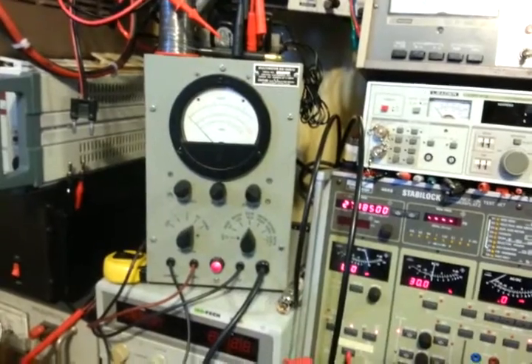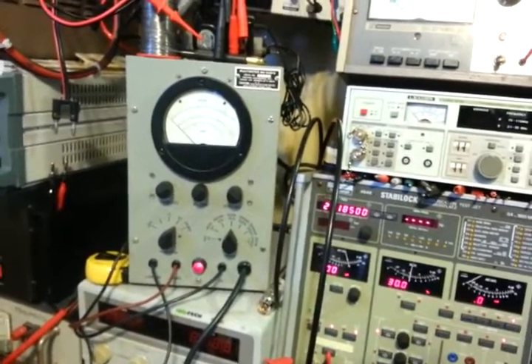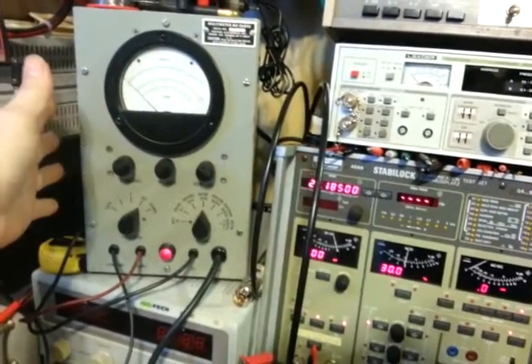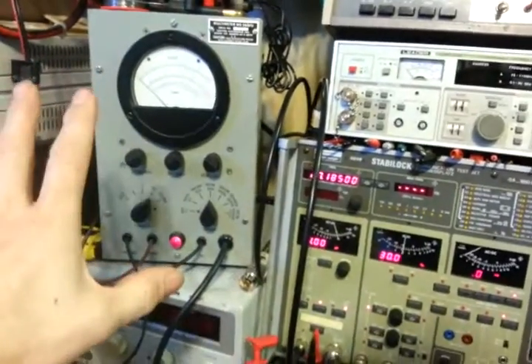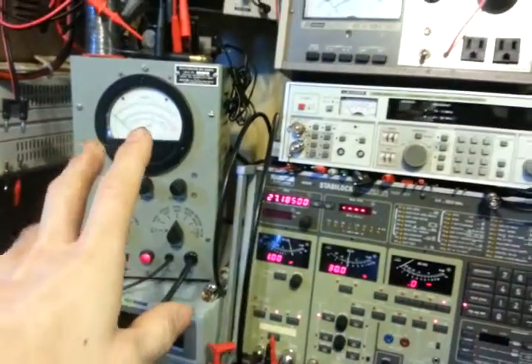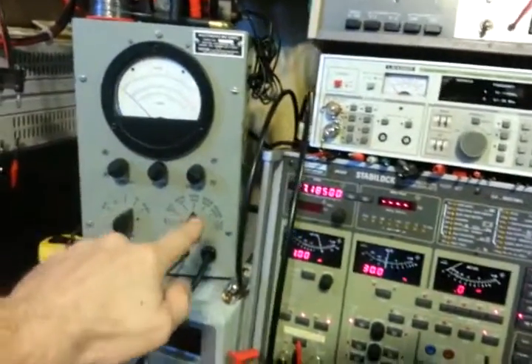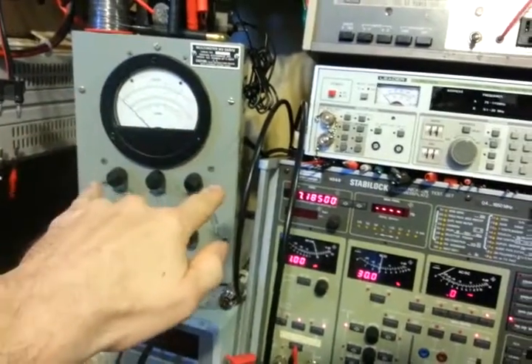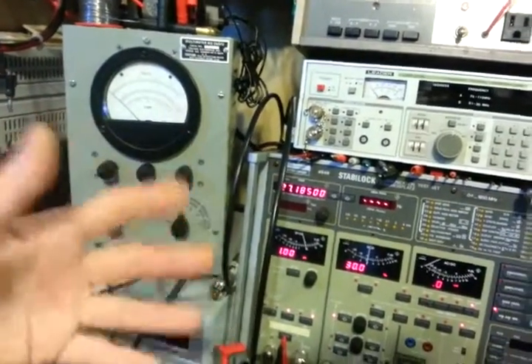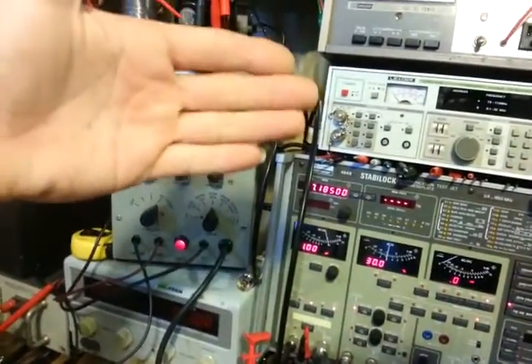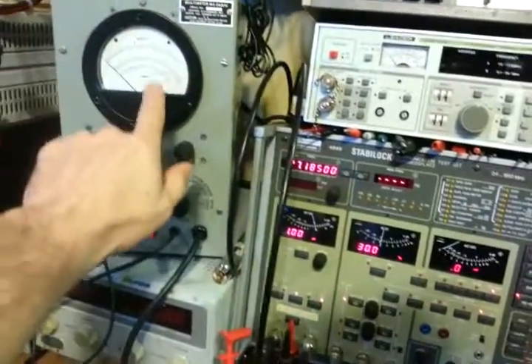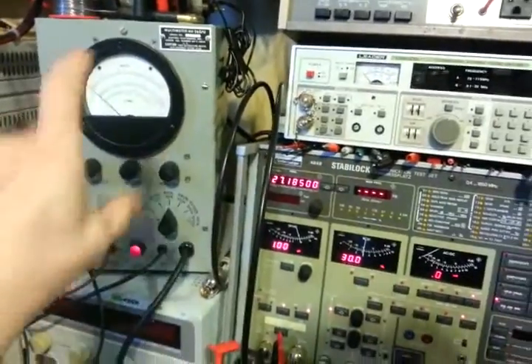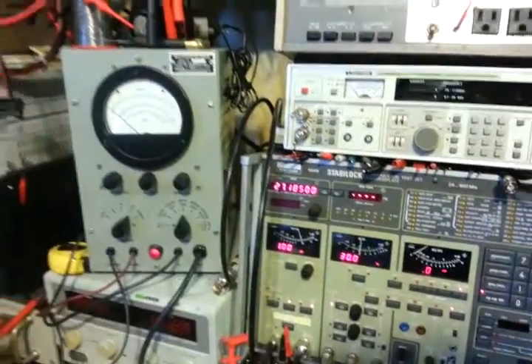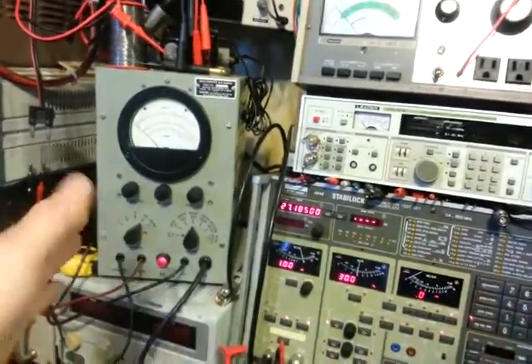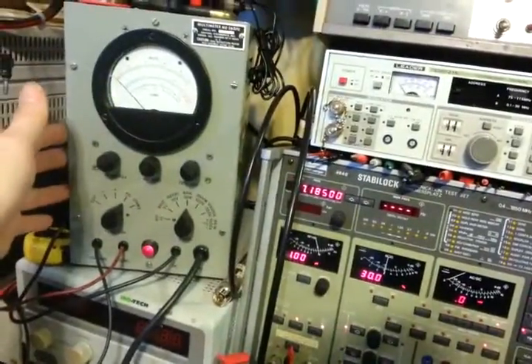Just, like I say, built a little bit more sturdy. And these, one of the main things is if you ever have to calibrate these, there's no disassembly involved. Unlike the other ones, they're a little bit more complicated to get to. This one, you just loosen 4 quarter-turn screws on the back. The back panel pops off, and every calibration adjustment's very easy to get to right at the top, and basically right behind this meter movement, facing backward. All the calibration adjustments are right there. So you don't have to do any disassembly at all of this meter to calibrate it.